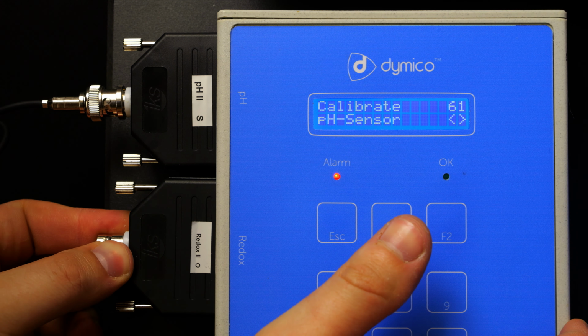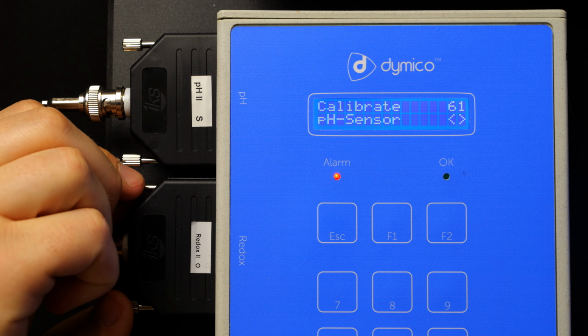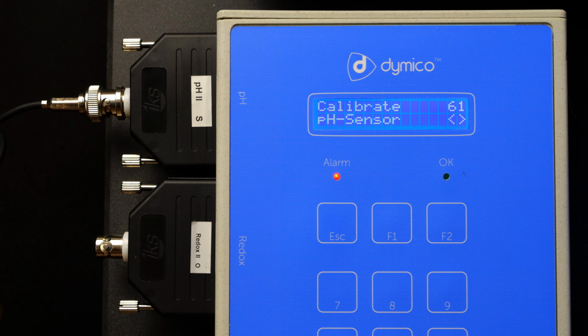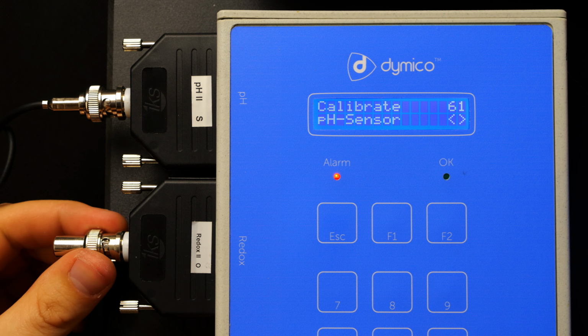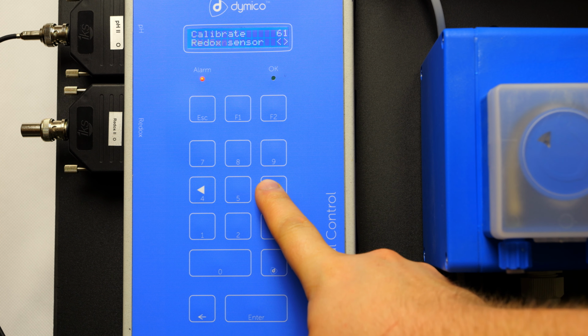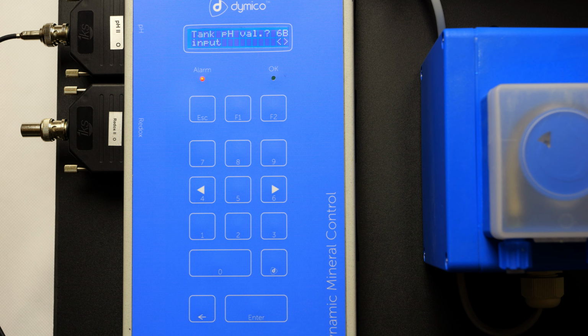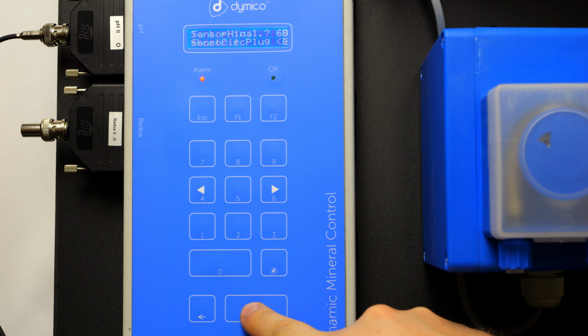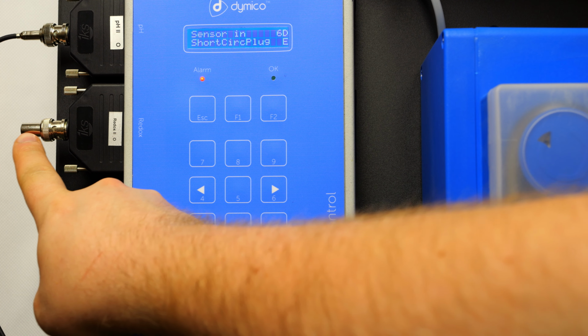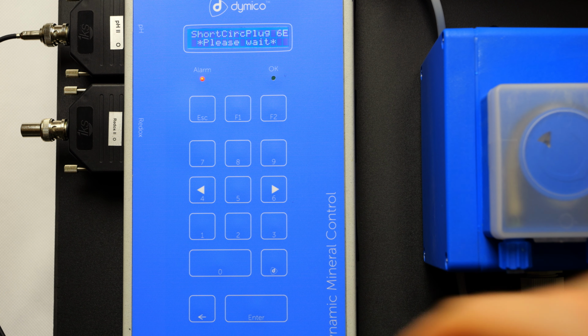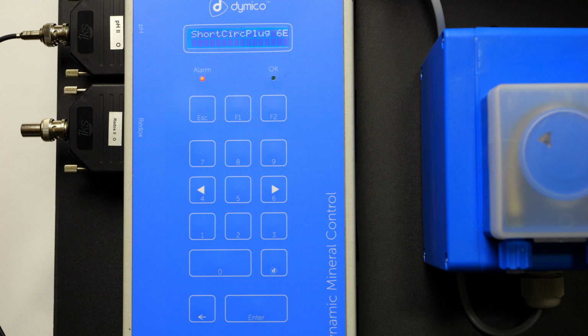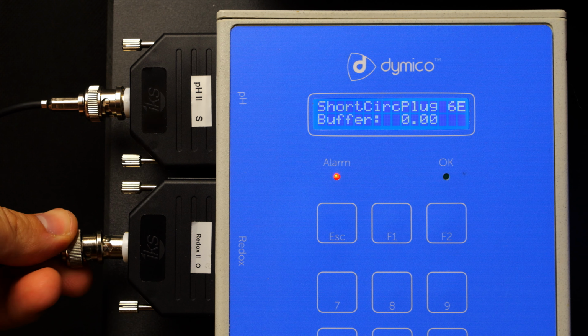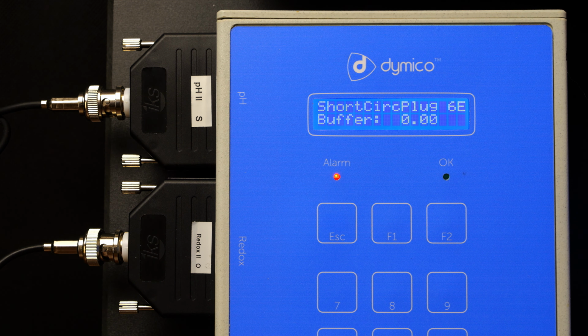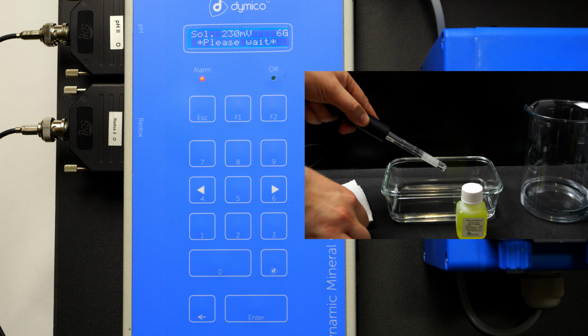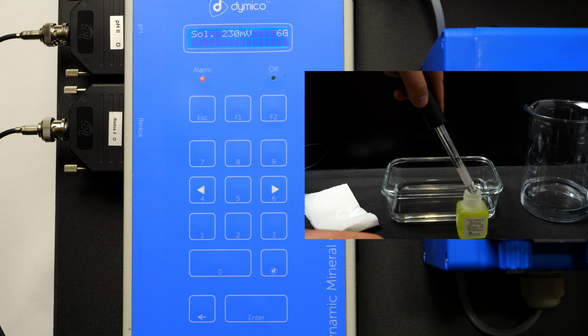Once the pH probe is calibrated, connect the redox module to the sensor 2 socket of the Aquastar. Connect the metal cap for the first point of the calibration. Navigate to main menu, calibrate, redox sensor, press enter. To correct the redox measurement according to pH value, select sensor 1 as input for tank pH value setting. After the first calibration point, remove the metal cap from the redox black module and connect the redox probe. Clean it and use a 230 mV standard solution for the second calibration point.